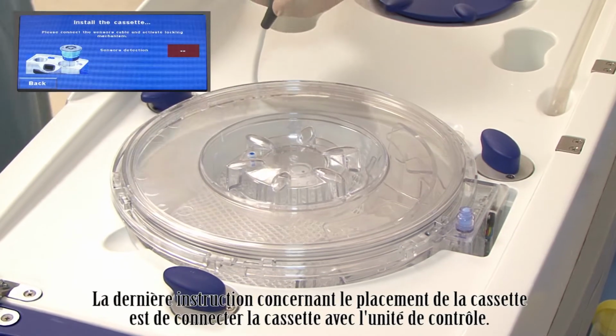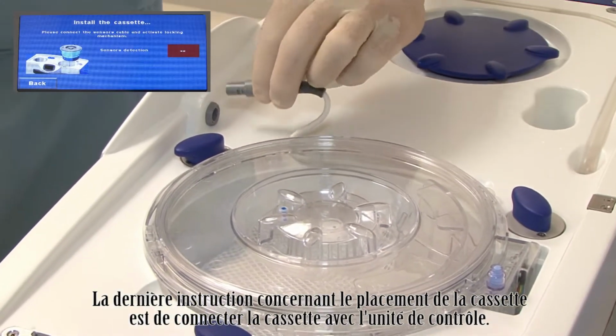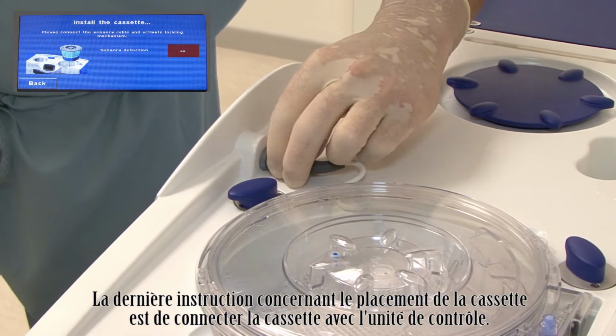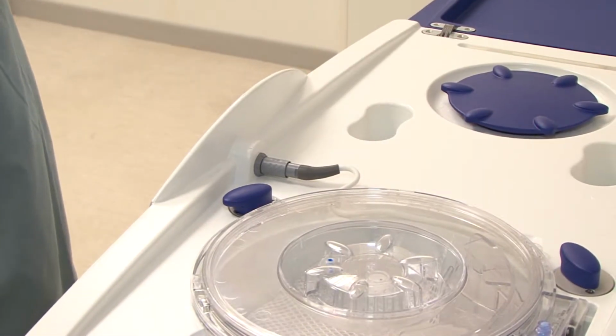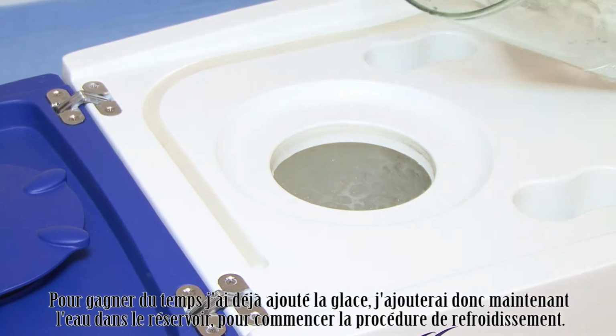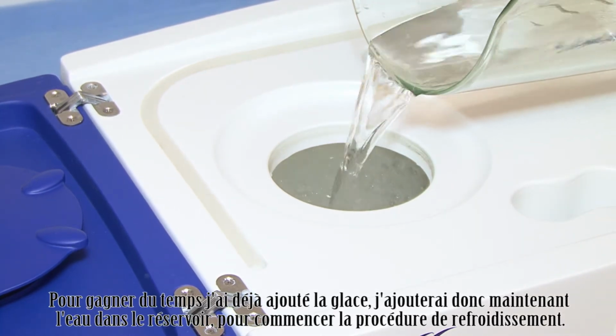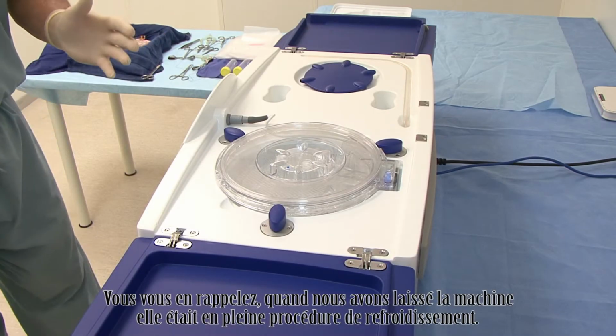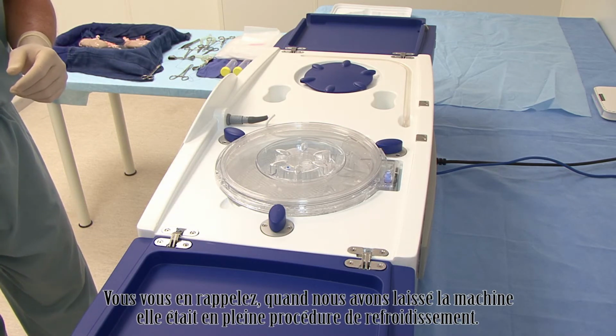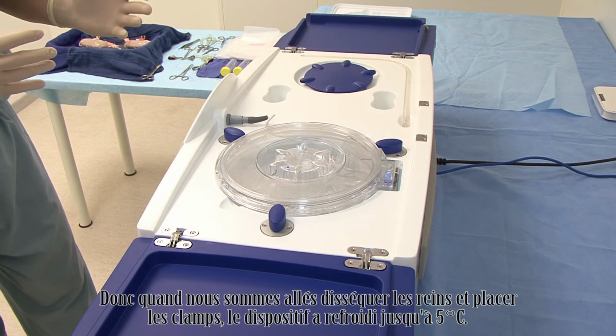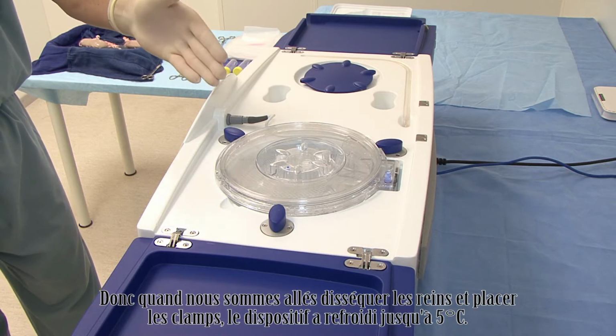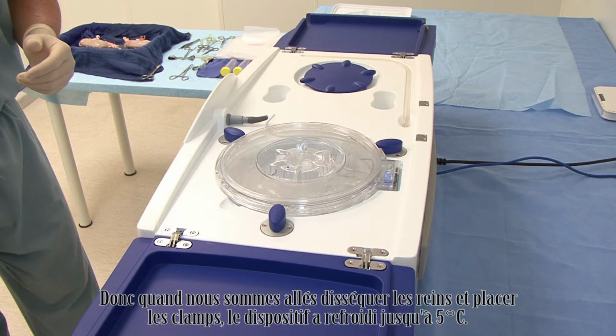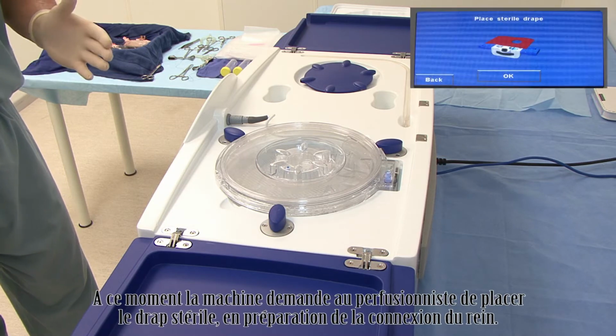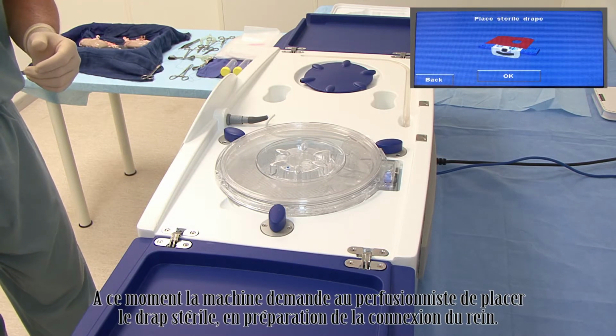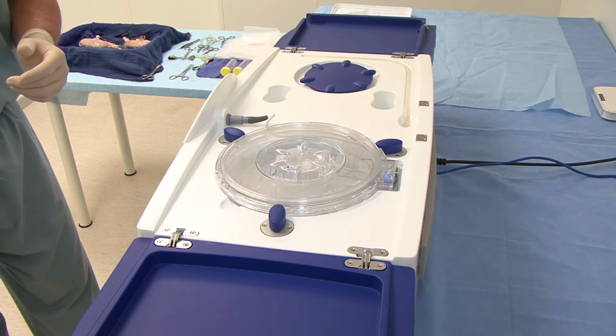The final instruction in the placement of the cassette is to connect the cassette to the control unit. So now I will add the water to the reservoir and initiate the cooling process. As you may remember, when we left the machine, it was in the pre-cooling process. So when we moved to dissect the kidneys and place the clamps, the device cooled to 5 degrees centigrade. At this time, the perfusionist will be directed to place the sterile drape in preparation for kidney placement.